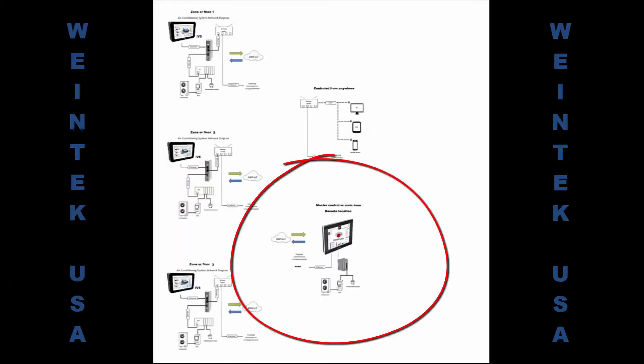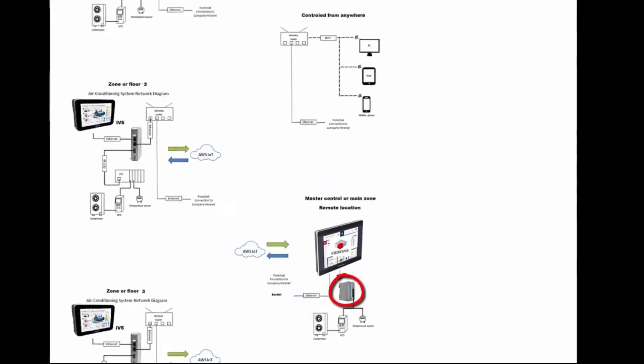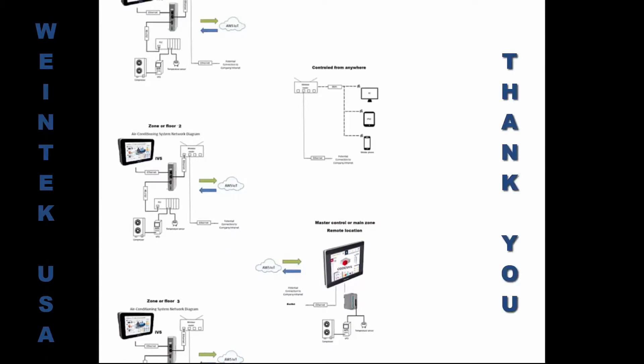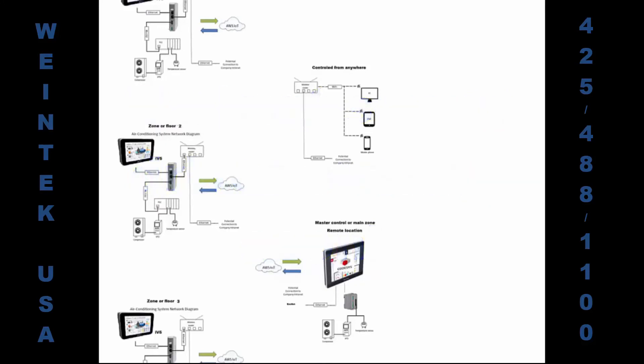Here we have an example of basically the same system, except on our master unit it's running CODESYS and connected to the IR series equipment. This solution offers the same remote capabilities as well as the ability to interact with each other remotely and through the AWS. The main difference is the elimination of the PLC from the system. We are also developing a BACnet server driver, which will be a nice solution for adding this equipment to existing building management systems.